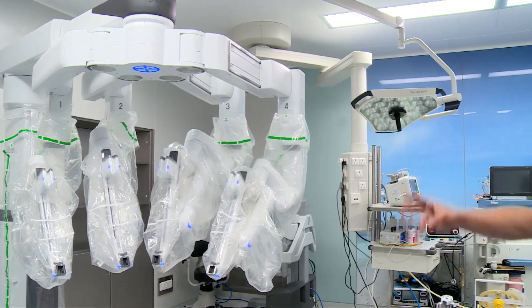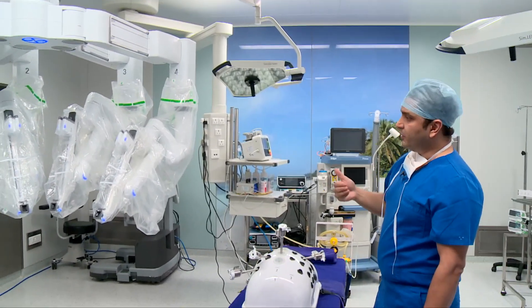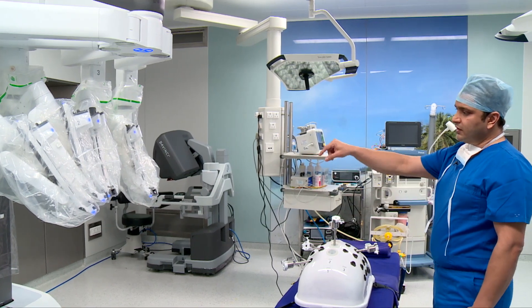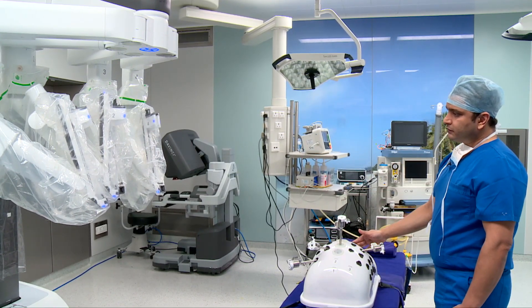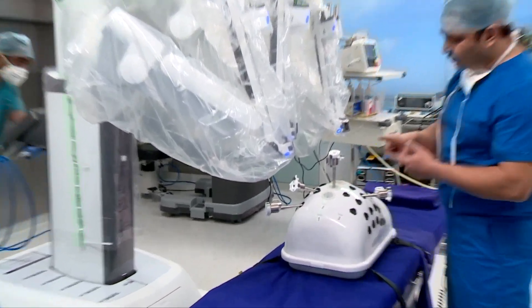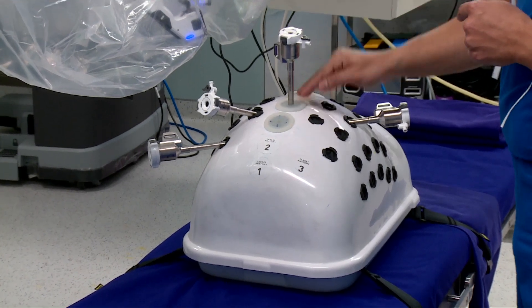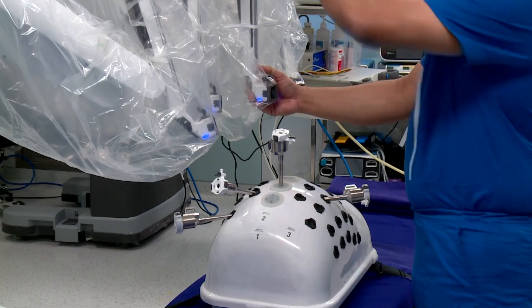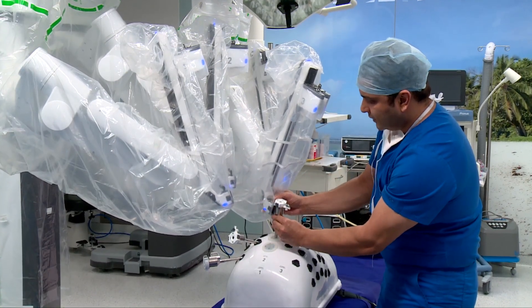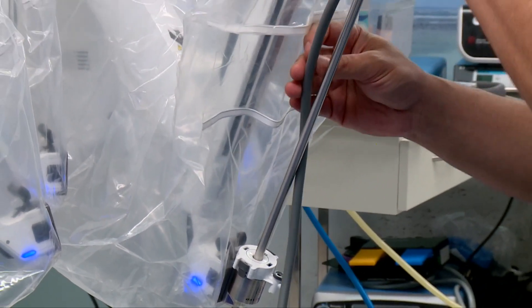The robot has a central pillar with a boom from which the four arms extend — numbered one, two, three, and four — and they are brought in close to the patient. Everything is controlled by the engineer and then by me. On the patient's belly there is a green laser light showing crosshairs, like what we see in a scope. Once that target hits where the camera is going to be, we stop the robot — that's the limit of how close it comes. Then we do what is called docking: we take the arms and dock them to the port using a magnetic device that clicks in. The robotic installation gives you lots of cues to guide you during the procedure.